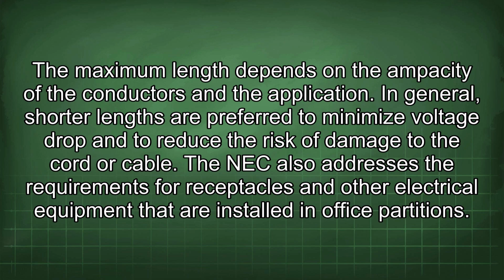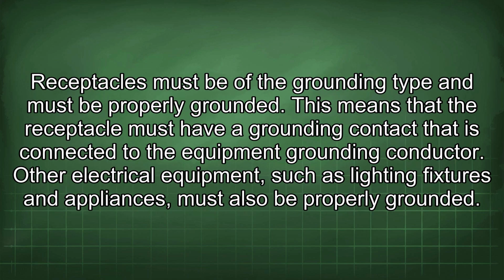The NEC also addresses the requirements for receptacles and other electrical equipment that are installed in office partitions. Receptacles must be of the grounding type and must be properly grounded. This means that the receptacle must have a grounding contact that is connected to the equipment grounding conductor. Other electrical equipment, such as lighting fixtures and appliances, must also be properly grounded.